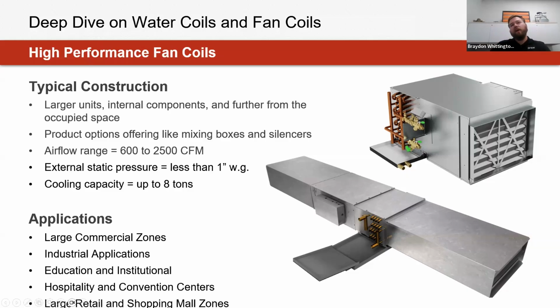And one interesting perspective there too for these silencers is that they've been specifically designed and tuned, I would say, for this product, where it's actually matching the flow positioning of where that flow is leaving that fan coil as it's going through the silencer itself, just to maximize the amount of attenuation that these components are really going to be adding on our system.